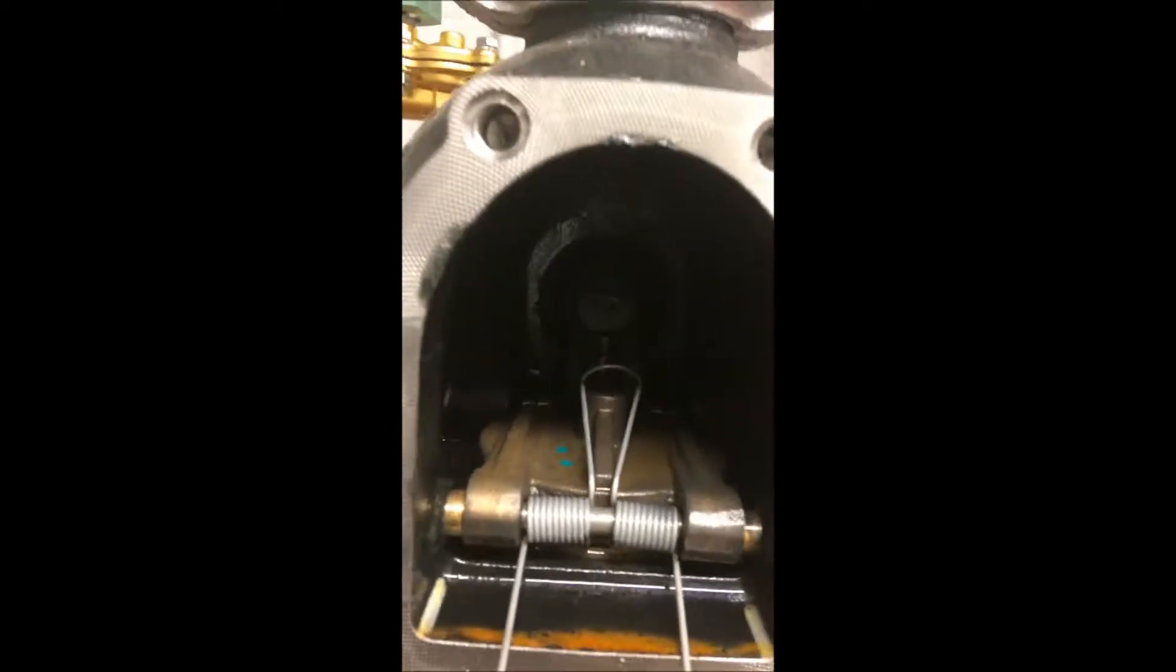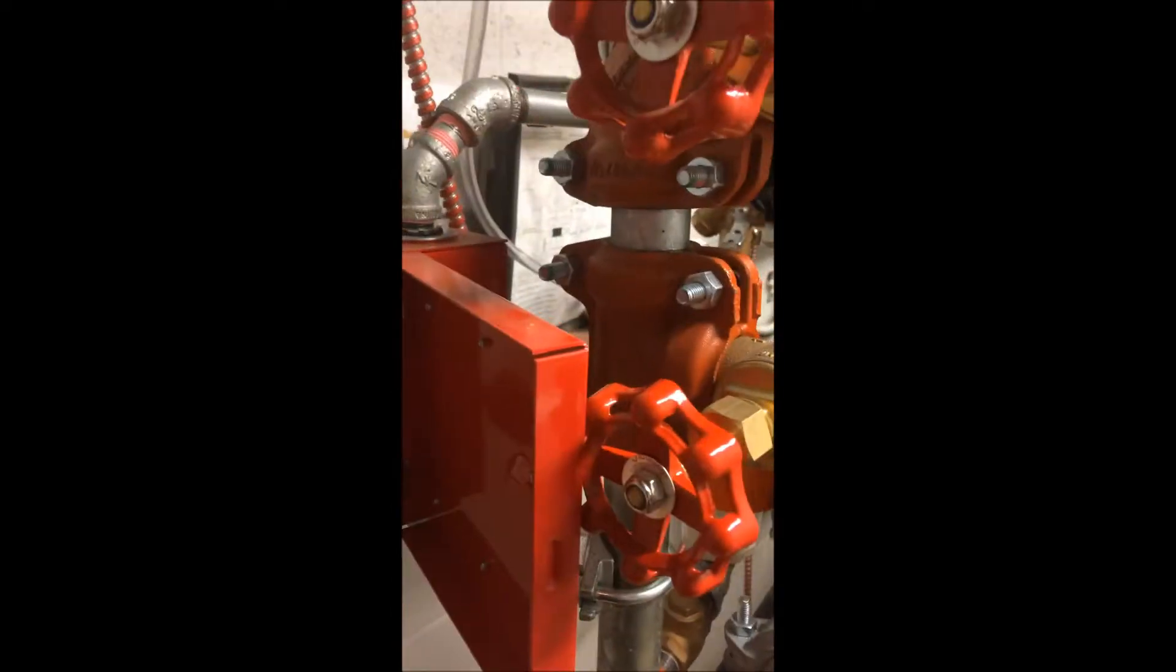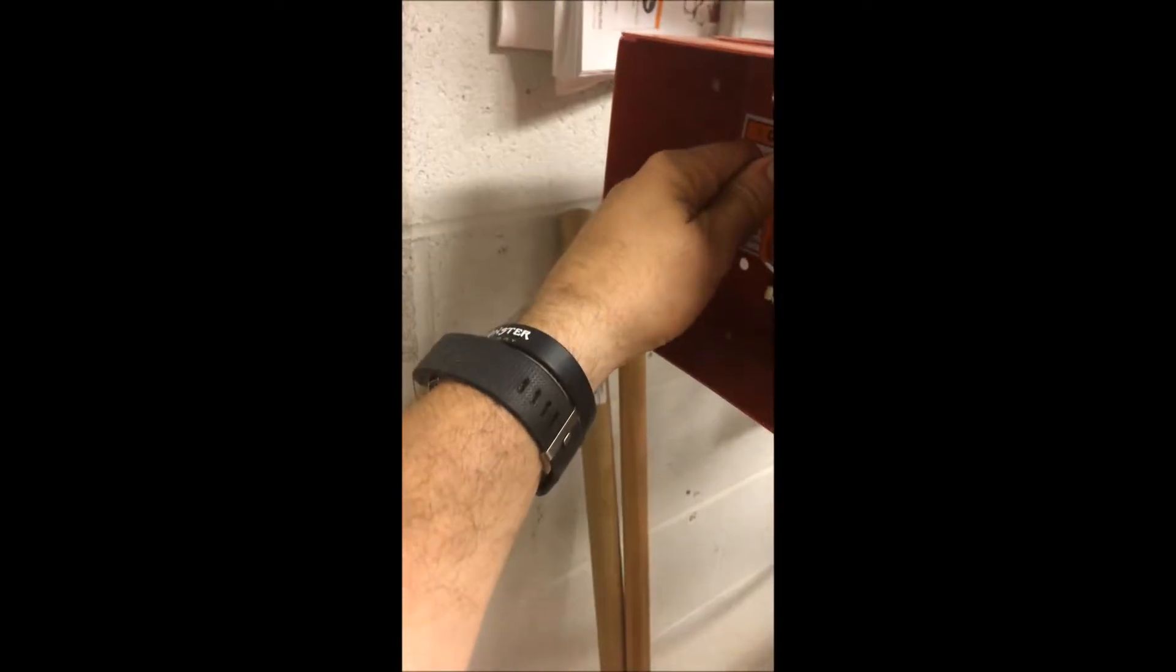Now, the nice thing about the deluge valves is we can actually load this thing with the face plate open. So, let's do that now. First thing we need to do is close off the manual release. That will allow pressure to be built. Now we're going to open up the constant water line.